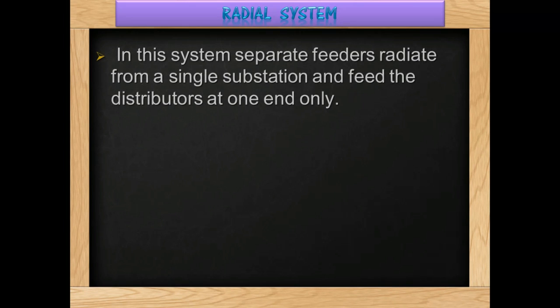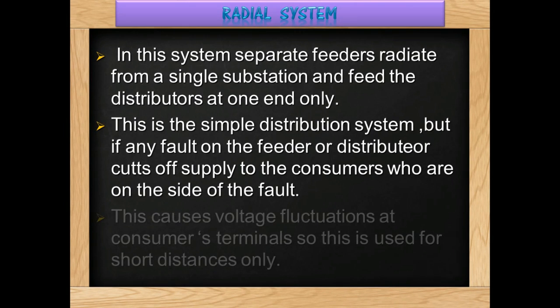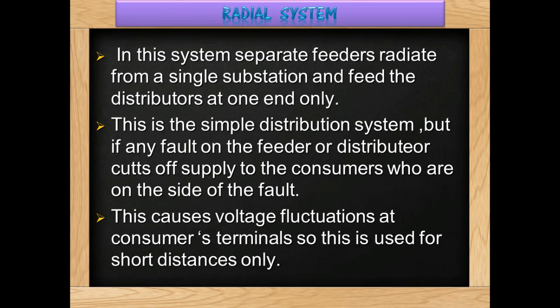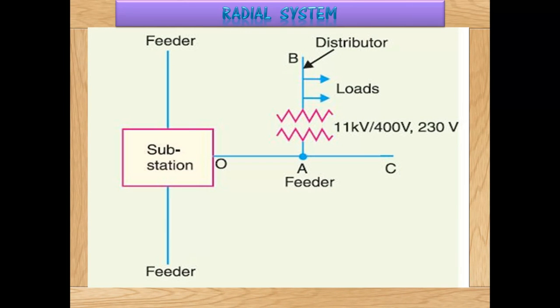Radial system: In this system, separate feeders radiate from a single substation and feed the distributors at one end only. This is a simple distribution system, but if any fault occurs on the feeder, it cuts off supply to consumers beyond the fault. This causes voltage fluctuations at consumer terminals, so this system is used for short distances only.